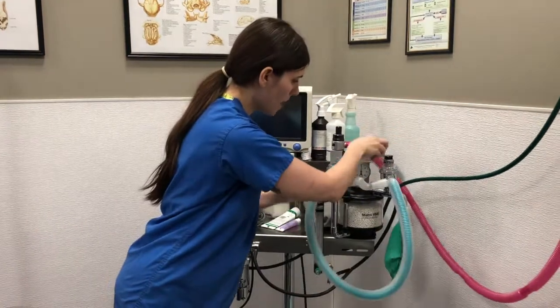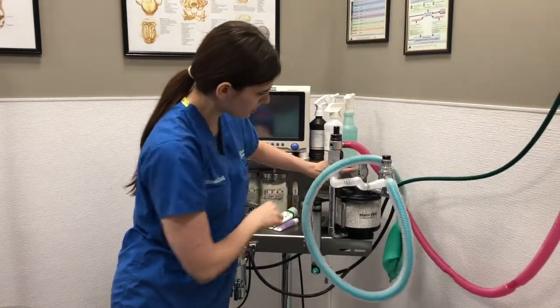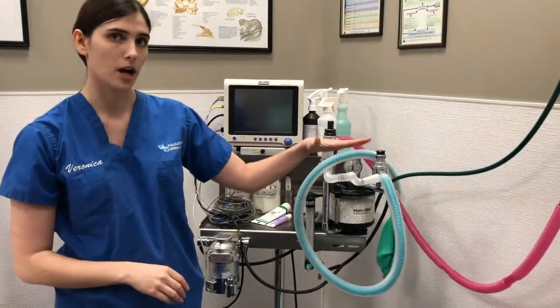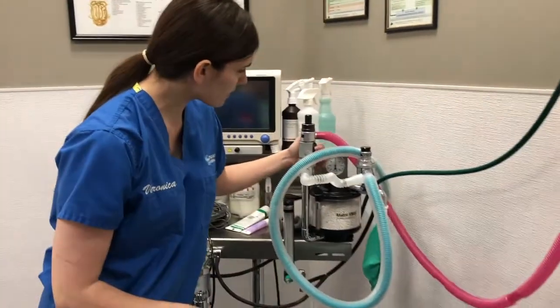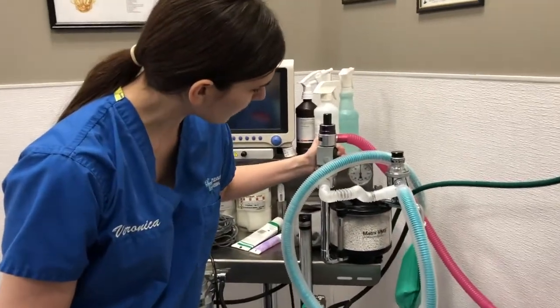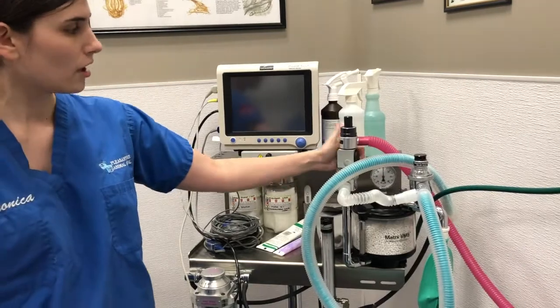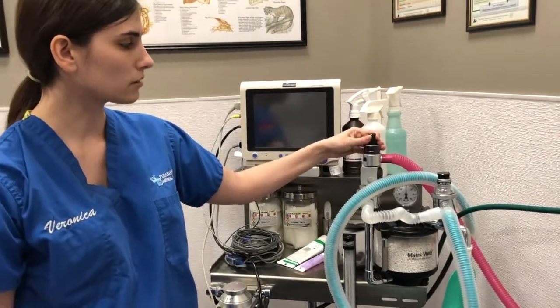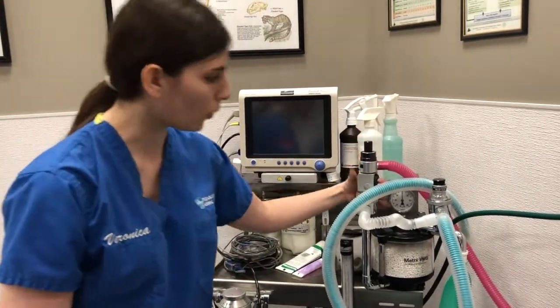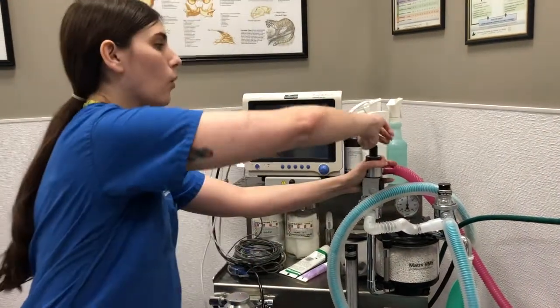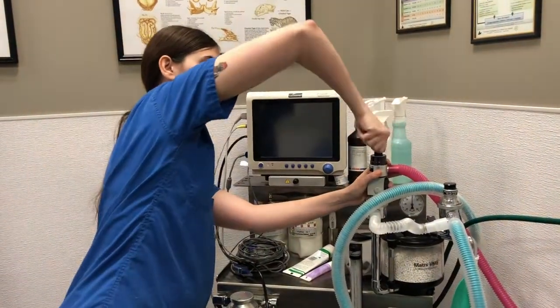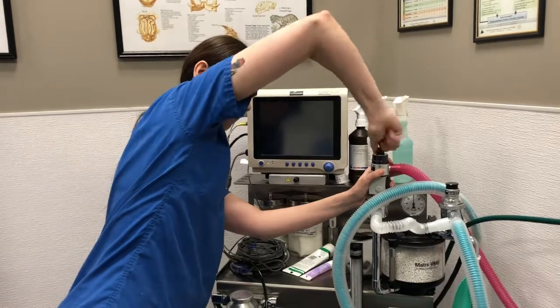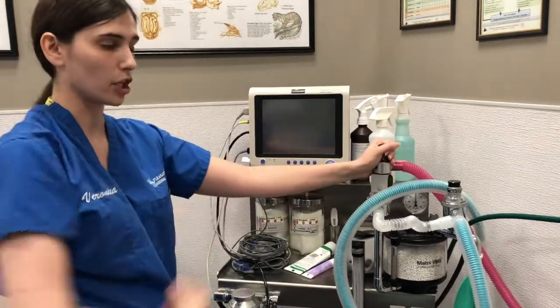Here we have our pressure valve. Usually when we're giving breaths, we want to make sure that the pressure valve does not go higher than 10. This is our pop-off valve here, which is a little button here. If we do have to give breaths or are checking the machine, we can hold this button here for easy access. Or with this knob here, we can completely close the machine, and this will send everything to the patient.